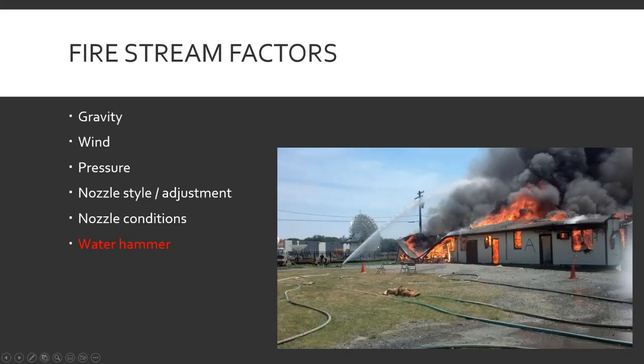Water hammer is highlighted as a special note. When you open nozzles, use a nice, easy, smooth motion. If you're slamming them open and slamming them closed — water is not compressible. So if you're flowing a lot of water and you slam it shut, all that force from the water hitting the now-closed nozzle goes back and can damage the pump, create a spike in pressure, and burst hoses. Just a nice easy smooth open and close — don't have to take two minutes, but try to avoid slamming it.